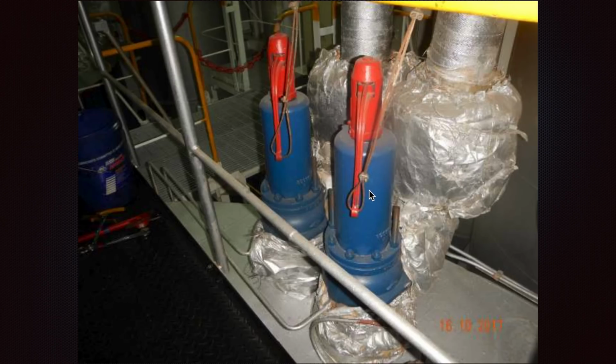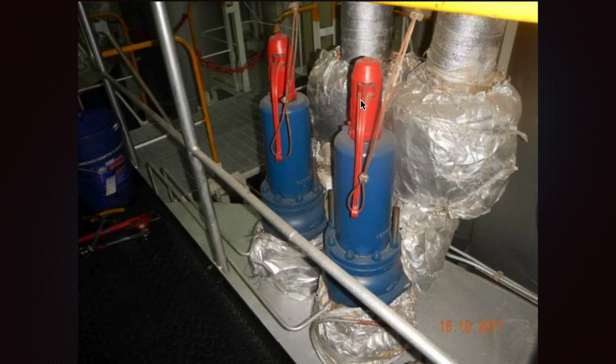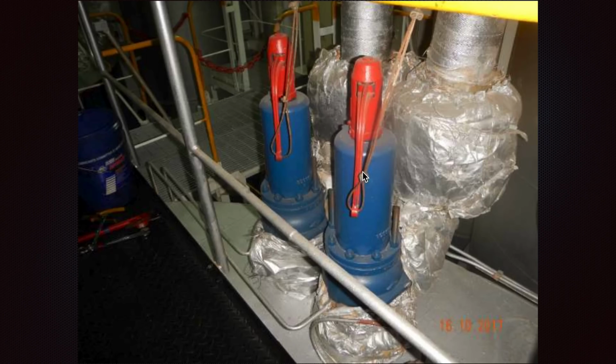So in that case, if the operator pulls the wire here, the lever will in some cases be bent to that position, because this lever only operates up and down. So the positioning and how everything is set up must be checked, and that's why we check the operation of the safety valves from a safe distance to see if everything is proper and working.